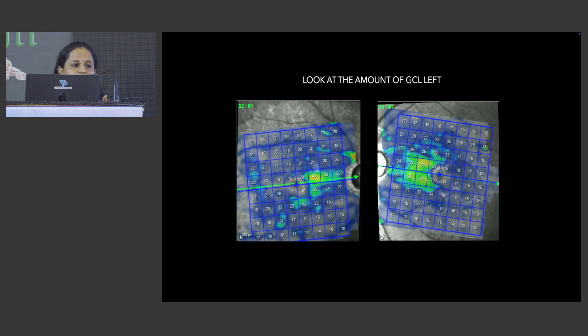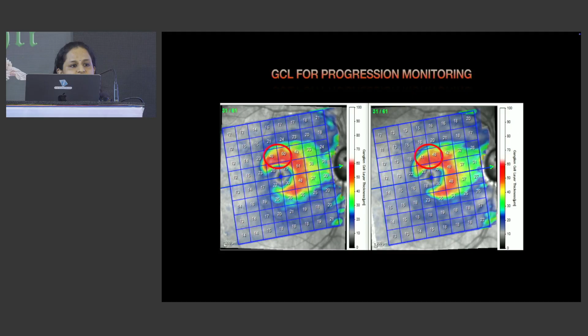And this can even be used for progression. This progression may not be seen evidently in the other tests. If you see the values here, 46 and 50, and in the second one 41 and 48, the Spectralis has an anatomic positioning system which takes the scan of exactly the same area the next time also. So this will be the exact area which is going to get scanned. Even with these slight changes, we can be sure that something is going on and we need to alter the treatment.